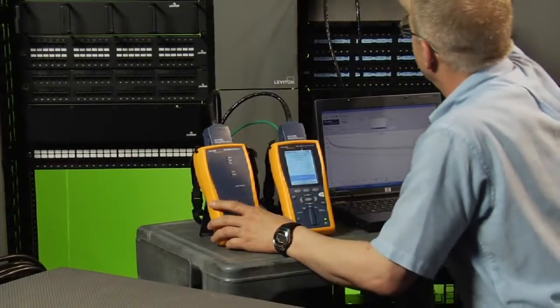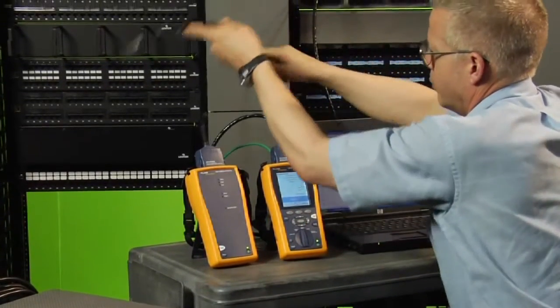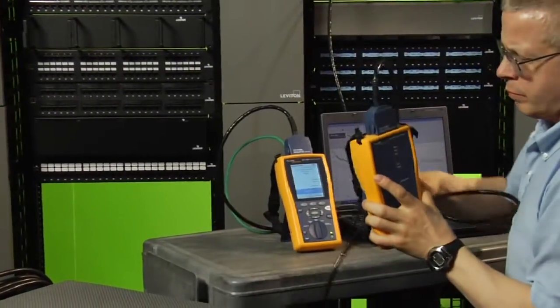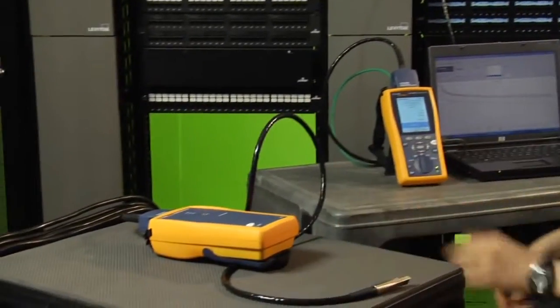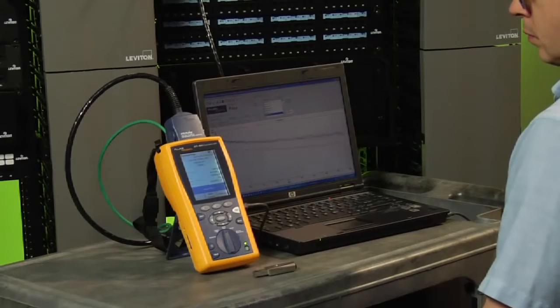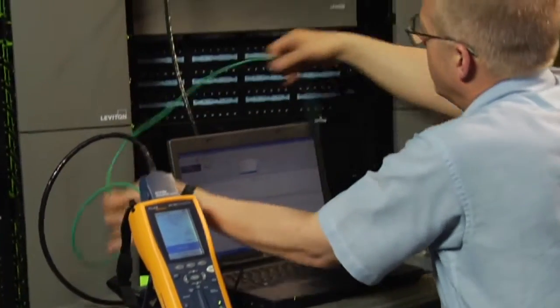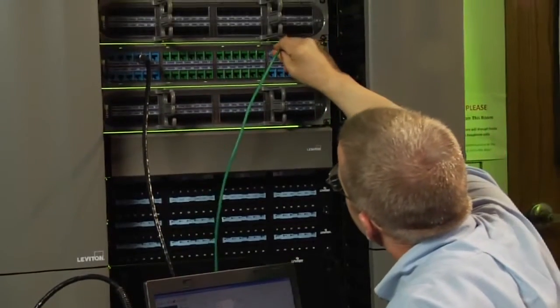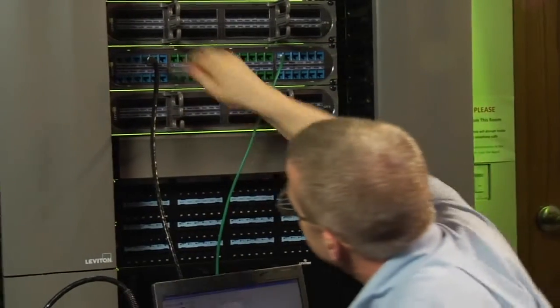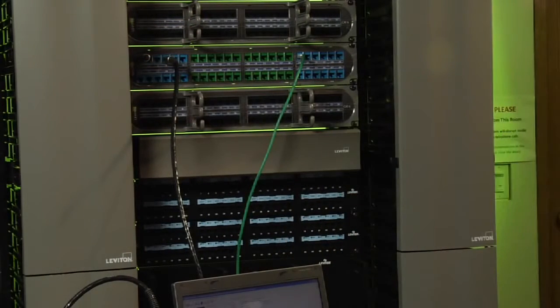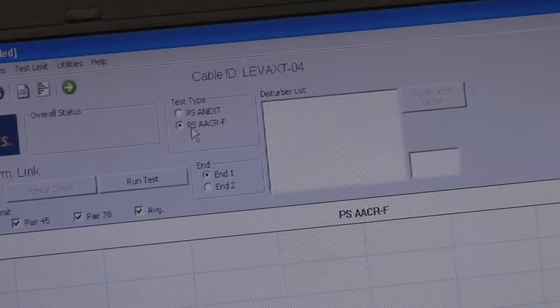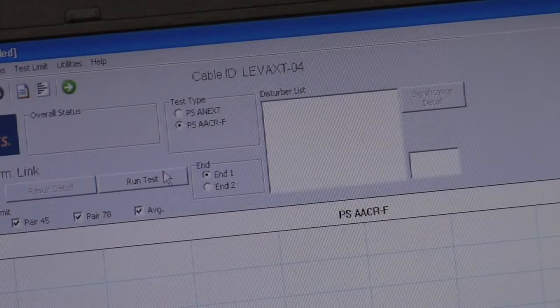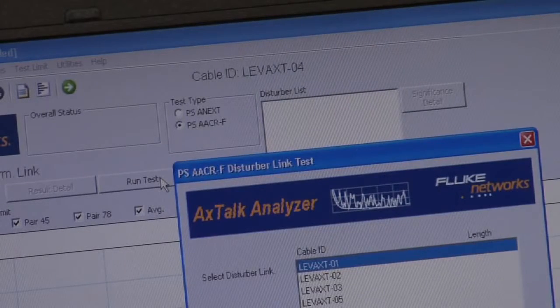The setup is very similar to the near end test, except we have to move the DTX remote unit to the other end of the link. The DTX main unit connection doesn't change. In order to synchronize the main and remote DTX units, we need to connect them up to a spare link, any link between the two panels but the victim or the disturber in the test. Use a patch cord at either end. Again, we terminate the disturber at the end where the main unit is plugged in. In our software, we change the selection to PS AACRF to indicate that we're testing from the far end, and we run the test.